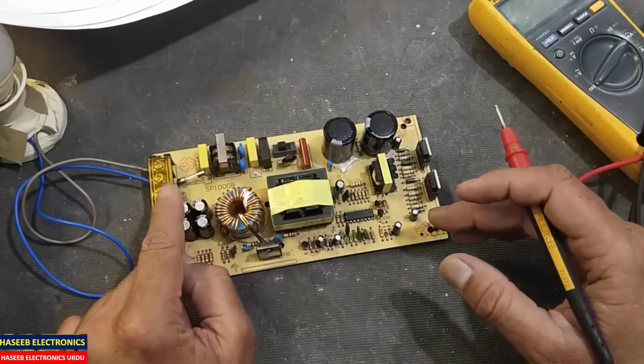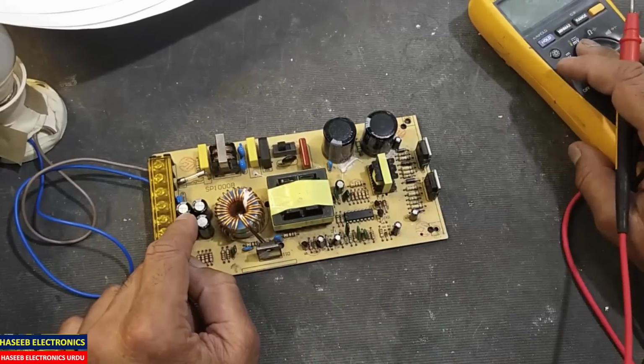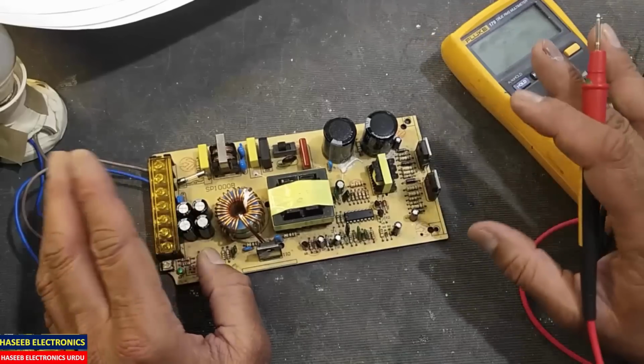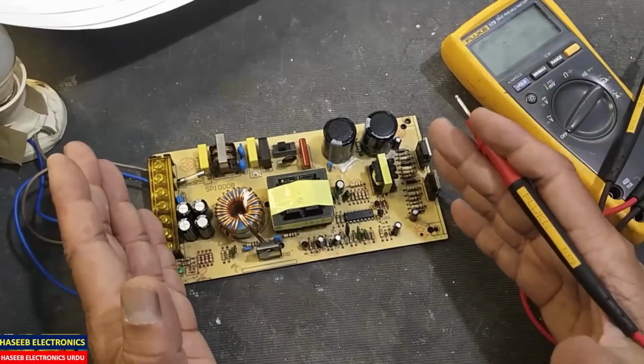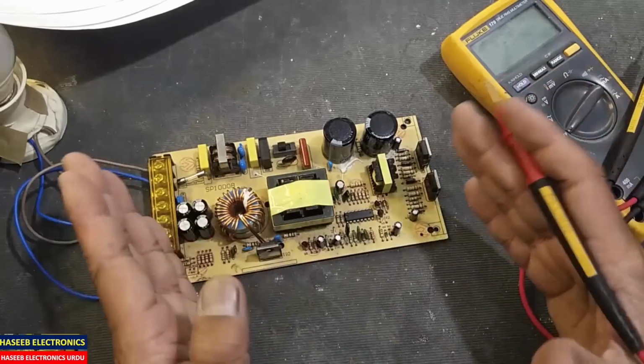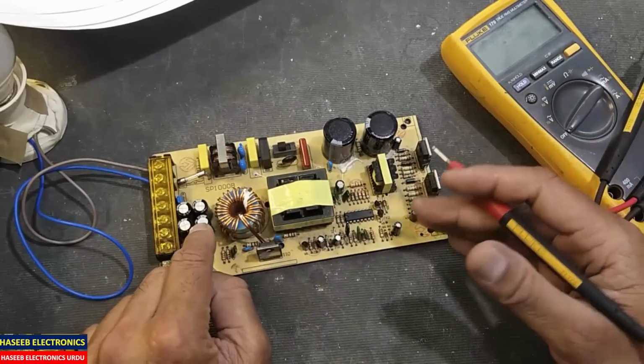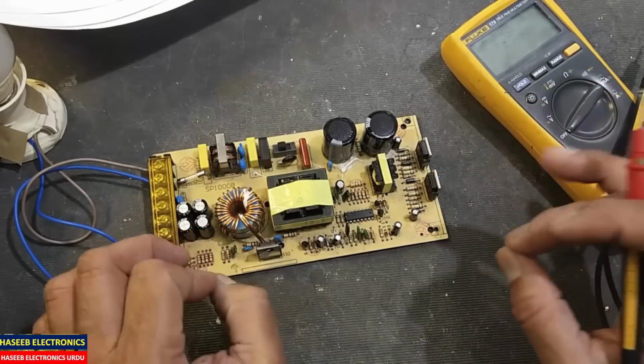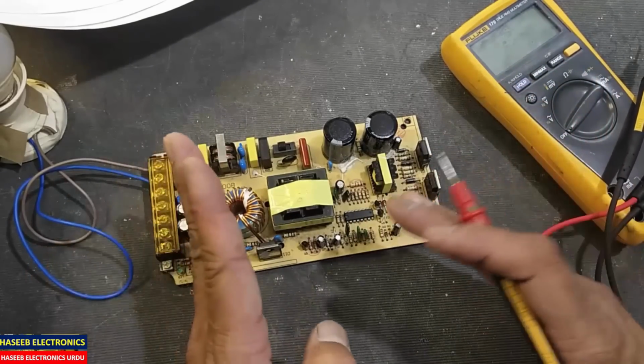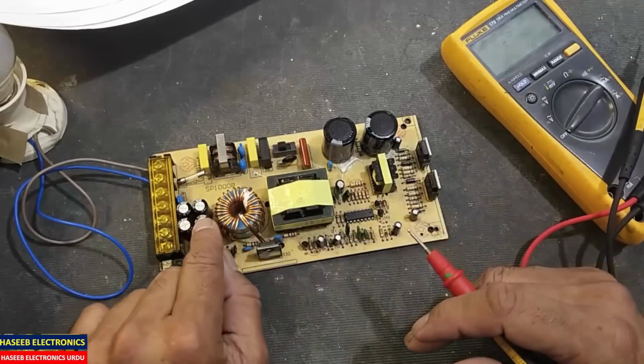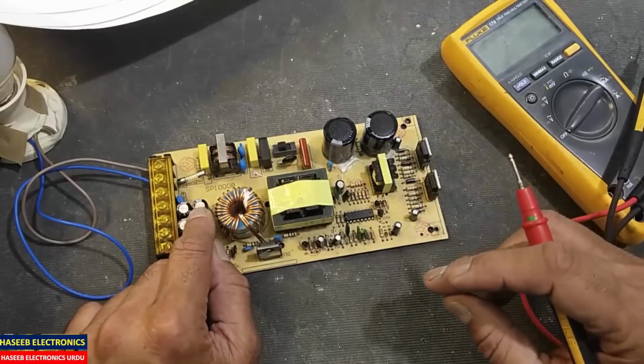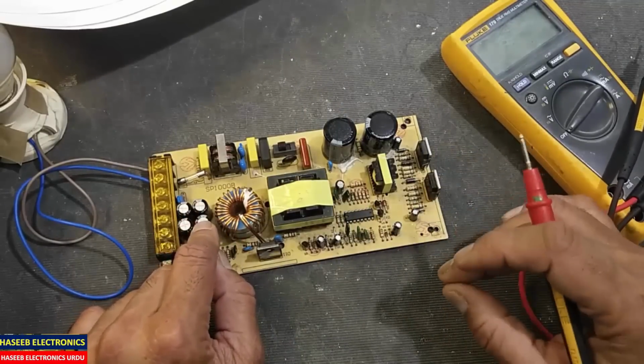If we test this capacitor with a multimeter, with capacitance meters, we will get approximately the similar value around its rated value, but for a functional test, it should be monitored at a high frequency test, at some rated frequency, and then its internal resistance will be verified.